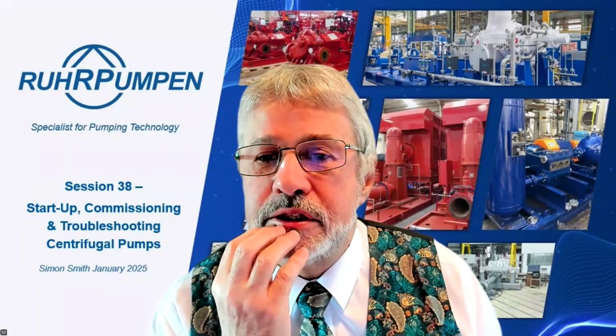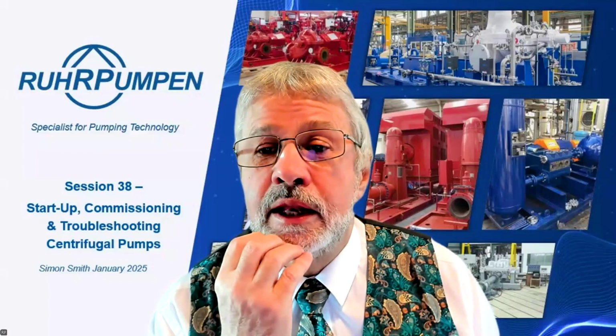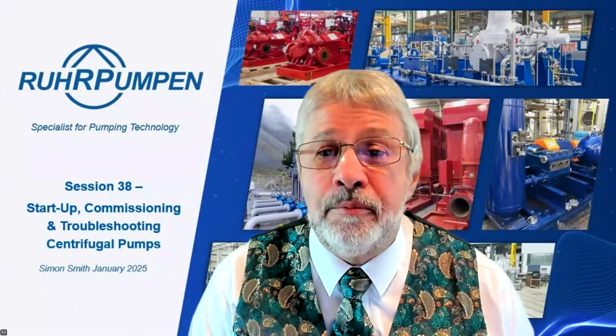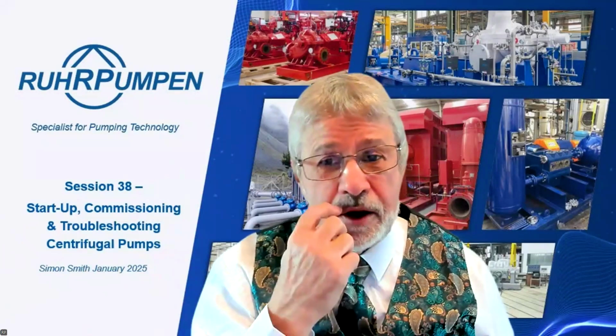If the pump is oversized, could the pipe connected to the discharge be rerouted by installing a T, keeping part of the flow going in its direction and connecting part of that flow to the pump inlet line? Excuse me a second. Yes, that would be quite a common thing to do. Take the amount of flow that you want to the process and the remainder goes through that T, maybe through an automatic recirculation valve back to the suction tank, not to the suction line of the pump unless it's well upstream. You don't want to circulate flow through the pump. So recirculating it back to the suction vessel would be ideal. Otherwise, to the suction line, but well upstream.